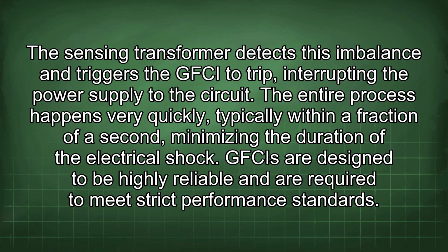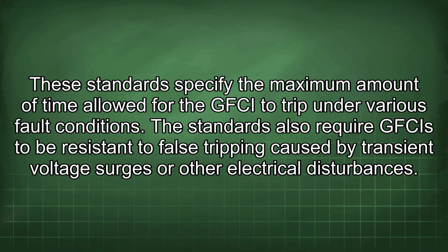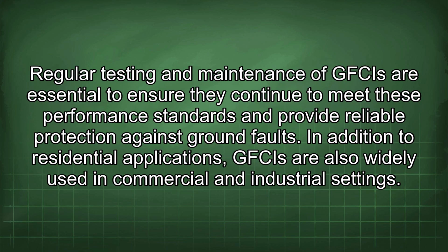The entire process happens very quickly, typically within a fraction of a second, minimizing the duration of the electrical shock. GFCIs are designed to be highly reliable and are required to meet strict performance standards. These standards specify the maximum amount of time allowed for the GFCI to trip under various fault conditions. The standards also require GFCIs to be resistant to false tripping caused by transient voltage surges or other electrical disturbances.